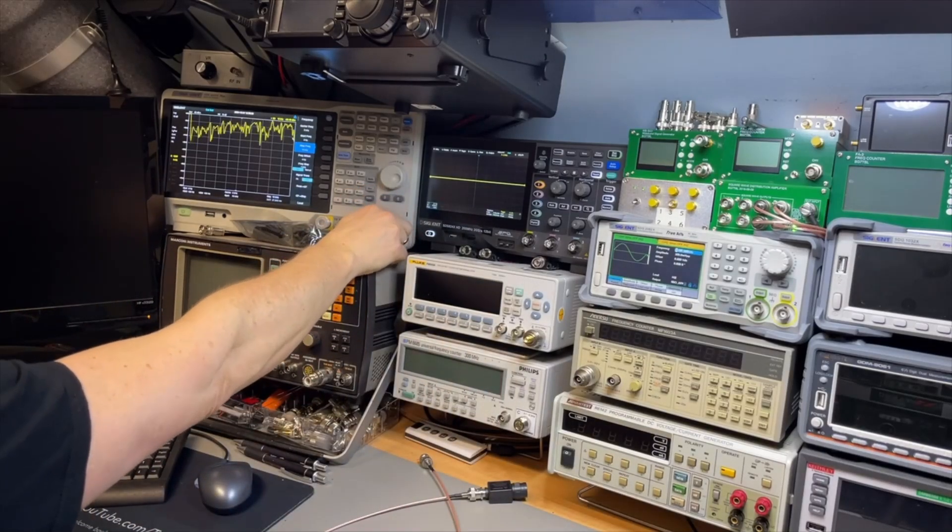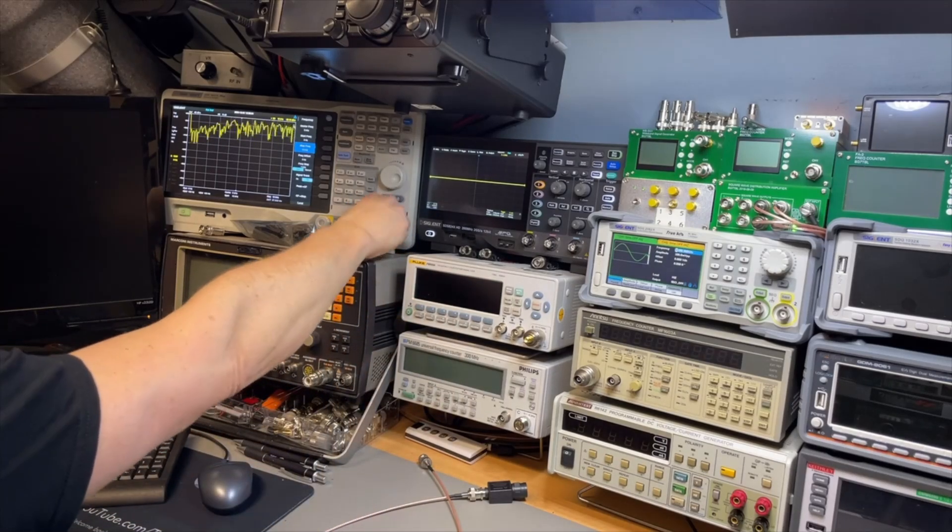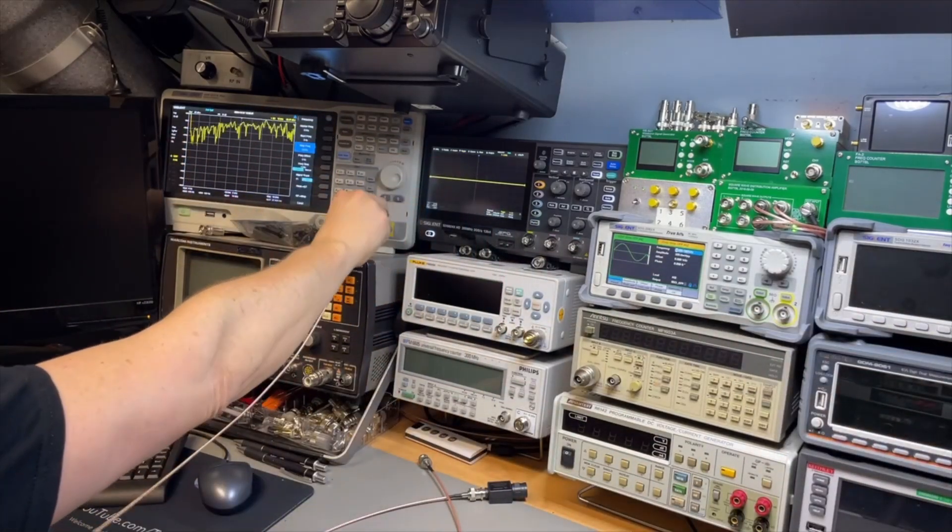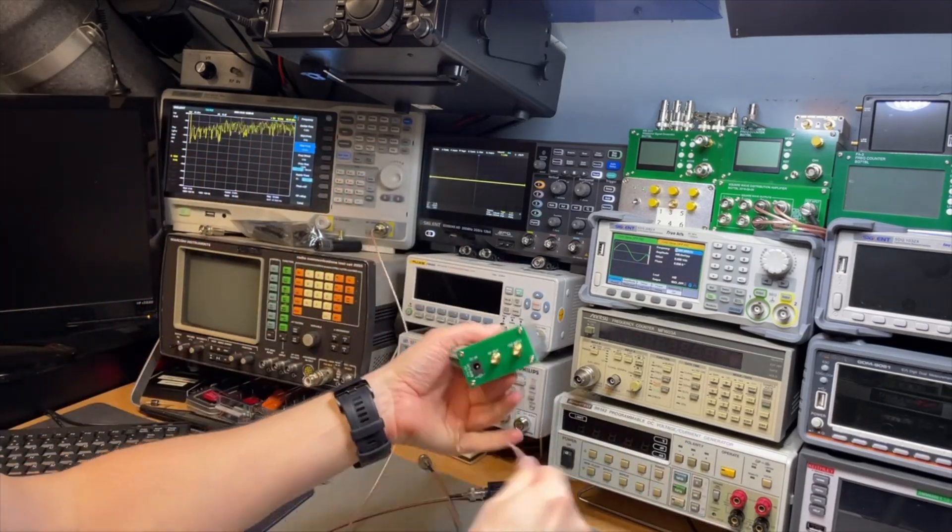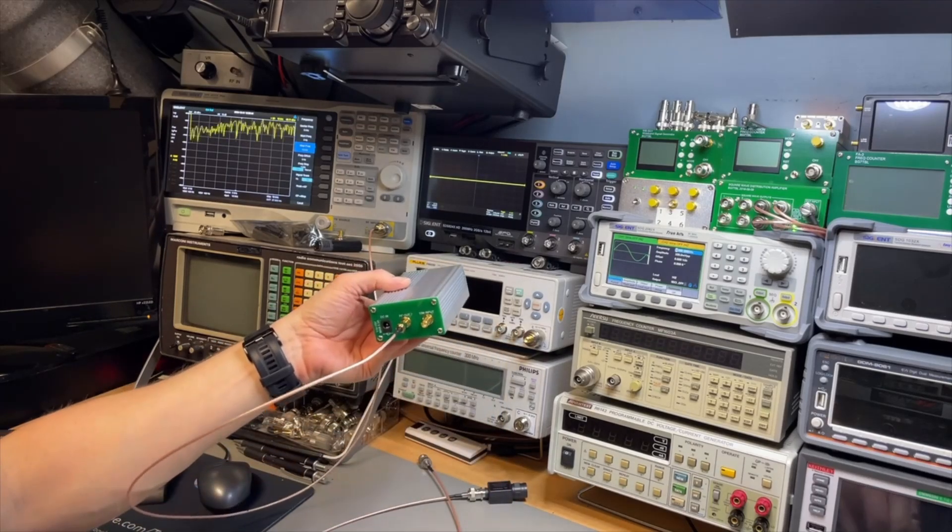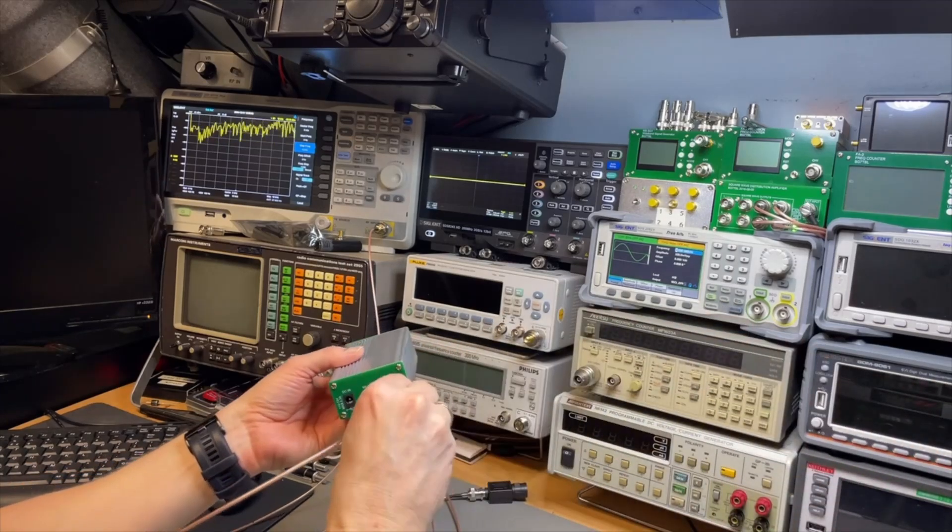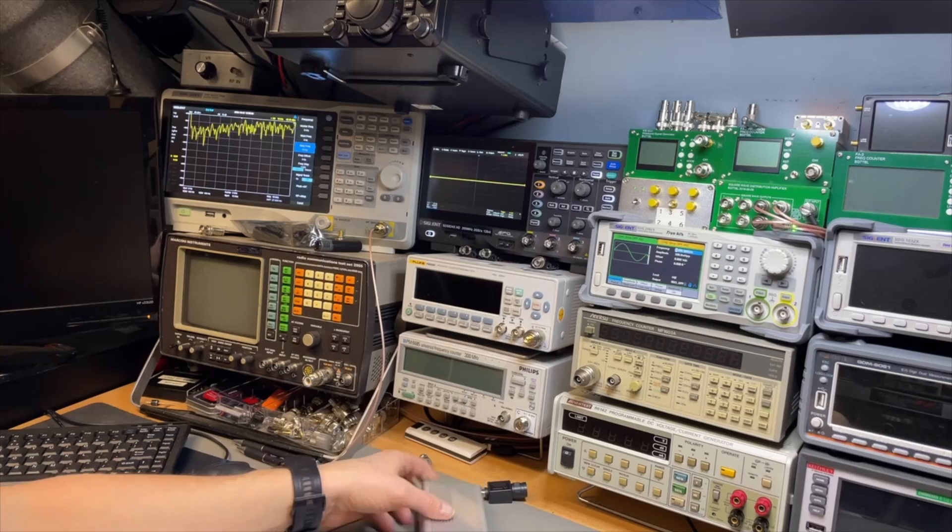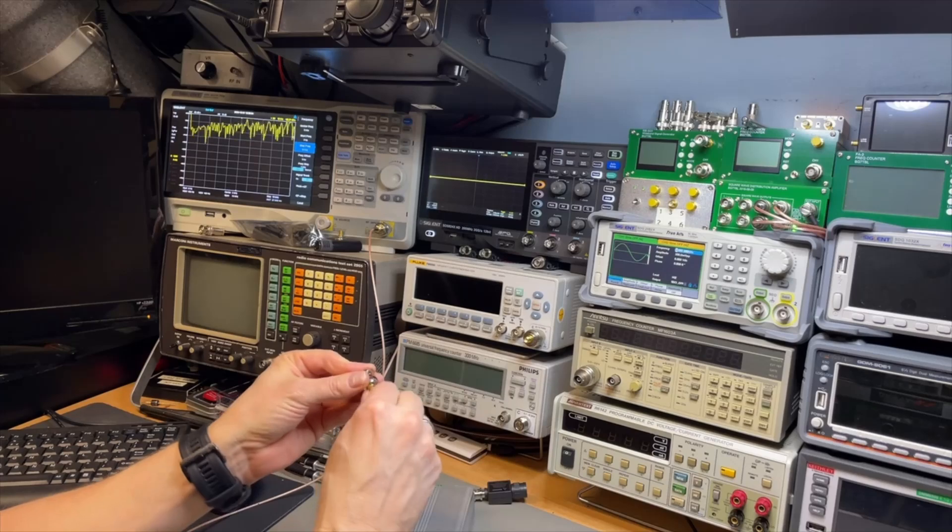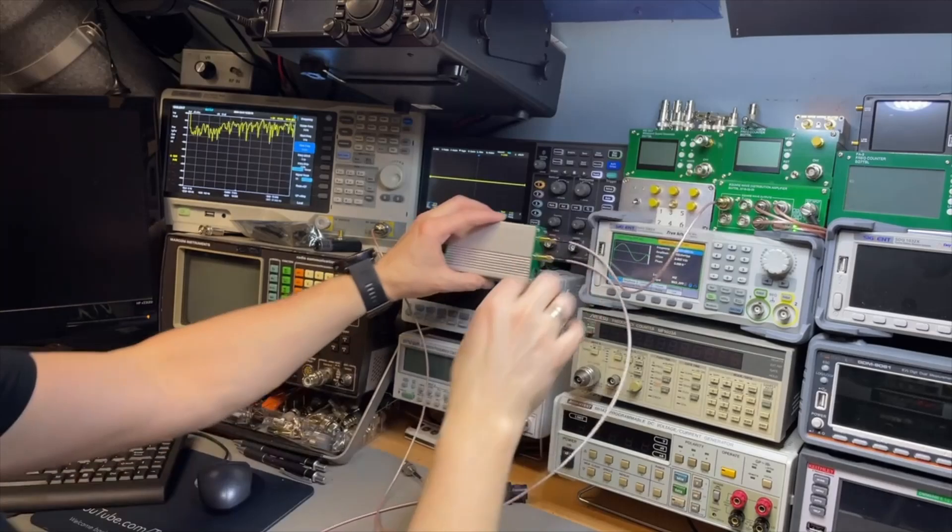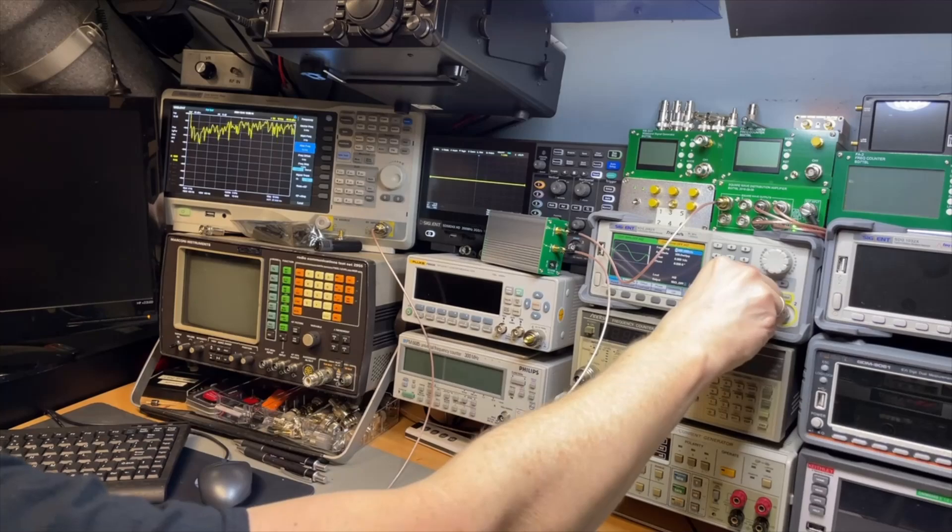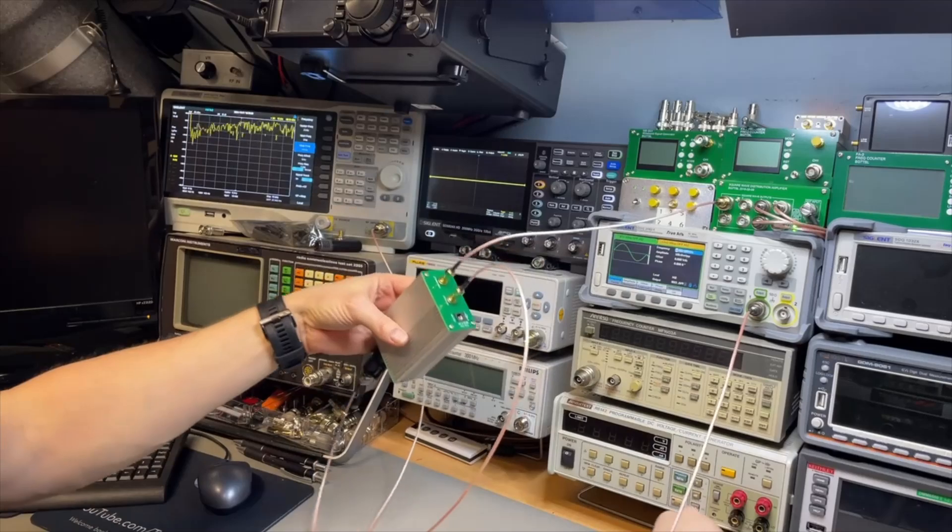So what do we do? We are going to connect the box to the spectrum analyzer. It came with this nice N connector. I will use the long cable for the spectrum analyzer. We put this in the RF output here. Then we have the 10 megahertz, I will put that in my reference. This goes here, and then we have our low frequency directly from that. I will put it inside the box here, and we need to power it of course.